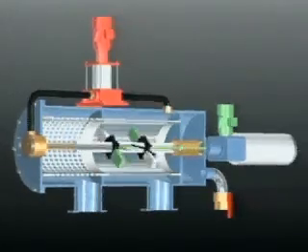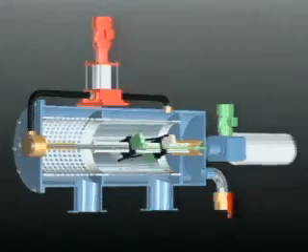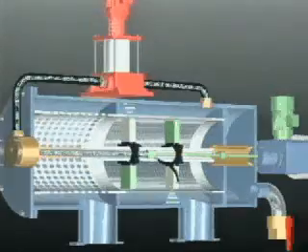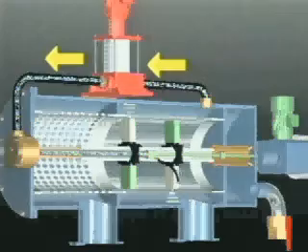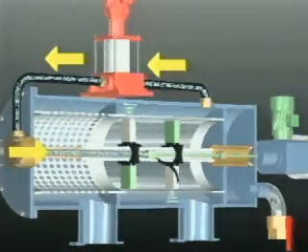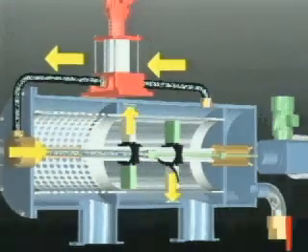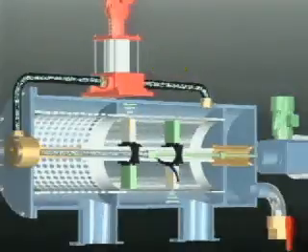This movement ensures that the back flush and the injection stream sweeps the entire area of the fine screen. A special injection pump sends pressurized filtered water through the collector's hollow shafts and into the spray nozzles, which spray it towards the screen.